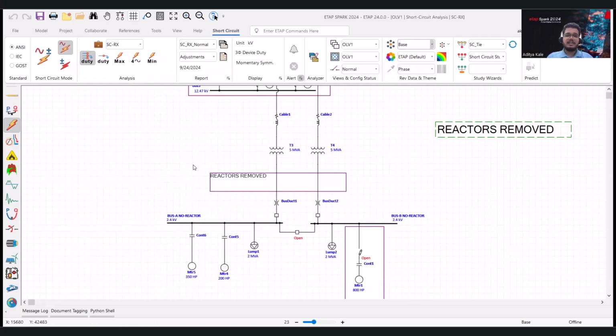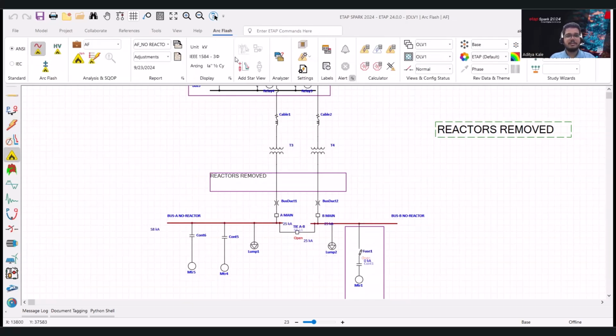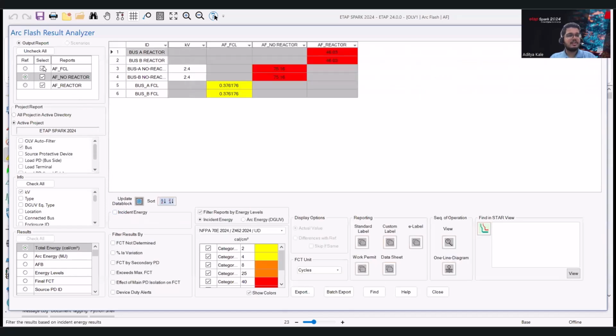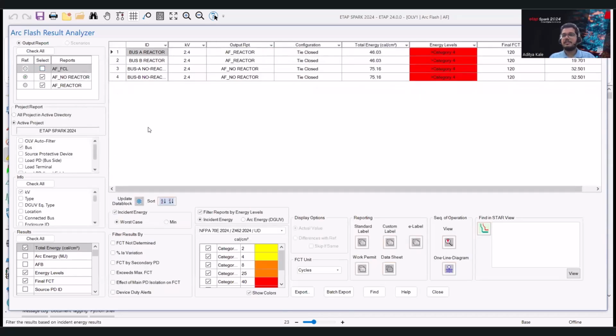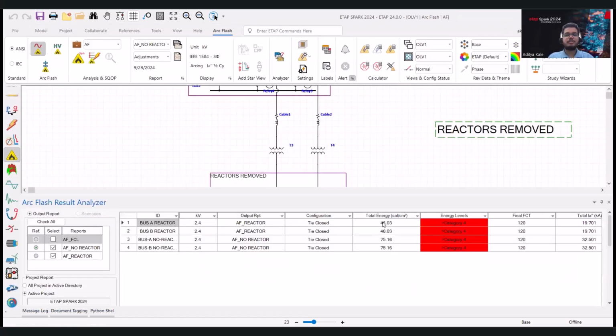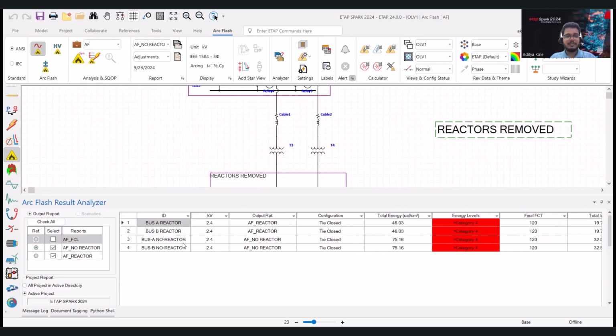Now we also know that increased short circuit is going to increase our arc flash results as well. So let's take a look at the arc flash results. I have the study set up. The analyzer will show us the results here. Let's disable the fault current. We'll look at it later. So what do we have here? If we take a look, the results don't look good. In both the scenarios, we have high arc flash incident energy. And we can see with the bolted fault being 19,000, it jumps up to 32,000 in the case for when the reactor was removed.